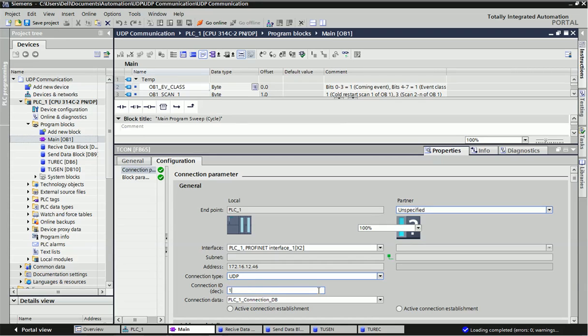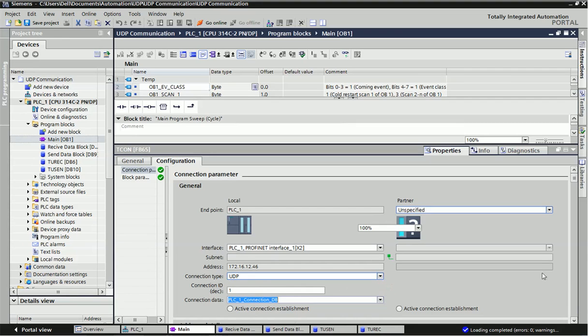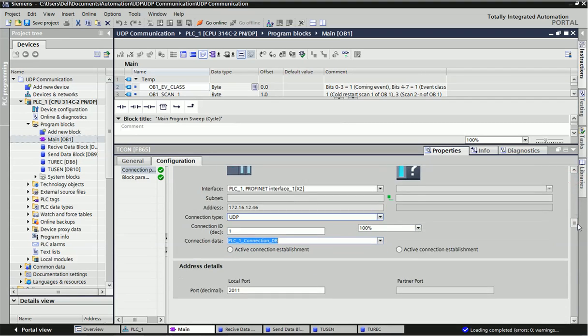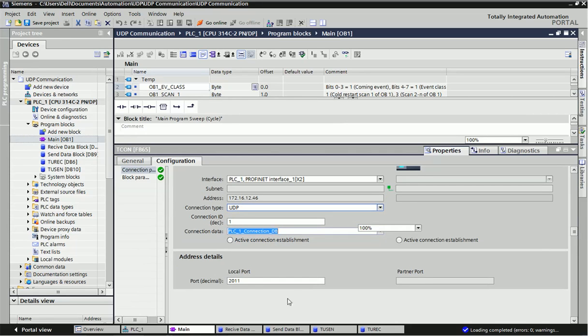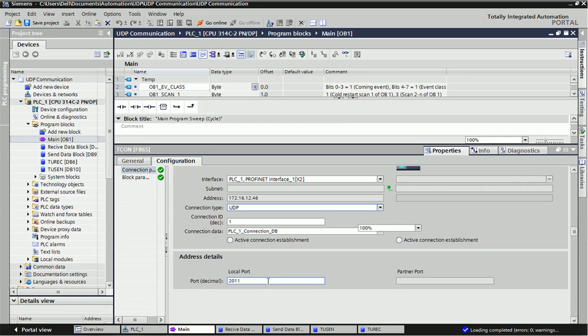The connection ID is taken automatically as 1, but you can change it as per your requirement. For connection data, selecting New will automatically create PLC_1_Connection_DB. I have already taken the connection data. The very important thing next is address detail — here there are two types of addresses: local port and partner port. I will assign the local port address, for example 2011. You can configure any local port address, and that address we will use for the UDP test tool as we will see next.